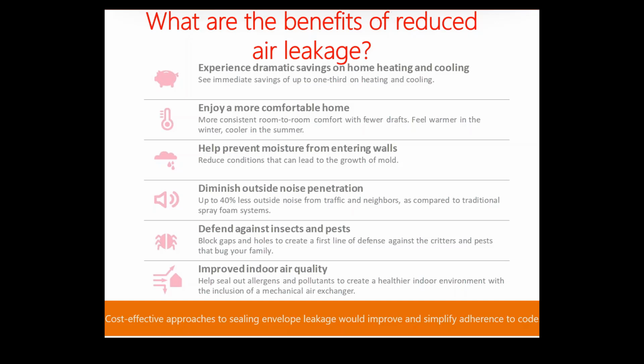One of the things you have to take into consideration is, if you look at the four walls of that uncomfortable room, usually there are two things that are stagnant or the same: your R value in your wall does not change unless you didn't put it in properly, and the U value and the solar heat gain coefficients on those windows usually stay the same. Depending on the type of windows, those could leak more than others, but the one part that's not a steady component of that room is the air leakage. So if you have unwanted hot and cold air coming into that room, no matter what you do to that room on the R value, it's hard to make that room comfortable. That's why air sealing plays a really important part in comfort.